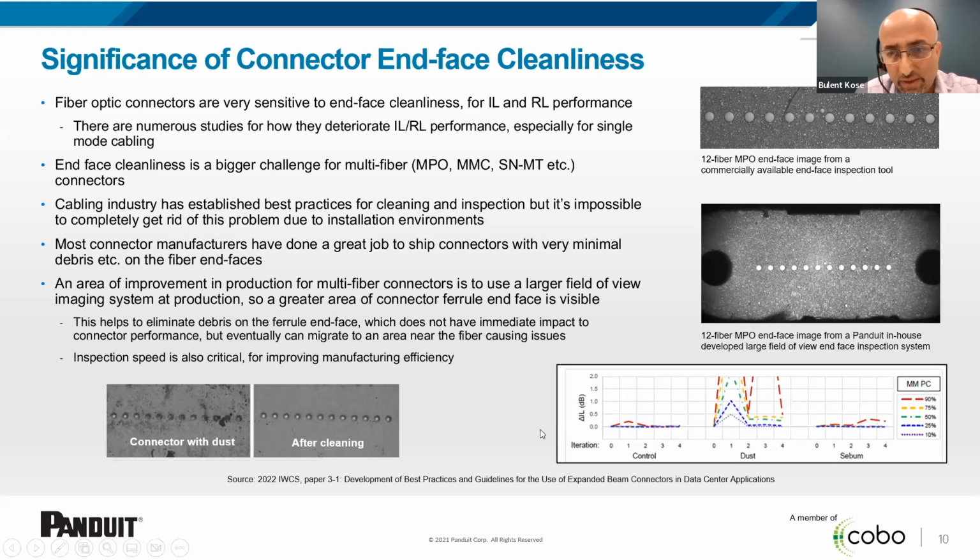At the bottom, I took some pictures from a very recent paper presented at IWCS that shows the impact of end-face cleanliness on insertion loss. You have the connectors with dust and after cleaning, and the insertion loss delta IL, the change. Let's look at the one in the middle, the effect of dust. Zero means it was a clean connector, and these different colors show different cumulative distributions for a large number of connectors. So it's a very small attenuation difference at X equals zero, obviously, at the beginning. Point number one is after there's some dust or dirt on these connectors, and then 2, 3, 4 is after they're cleaned.